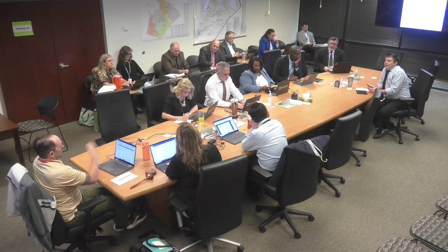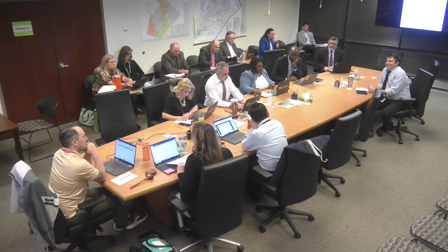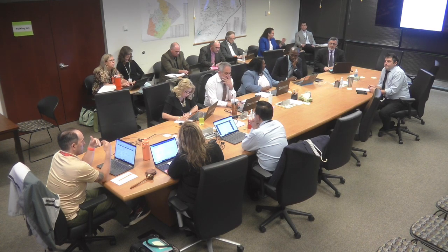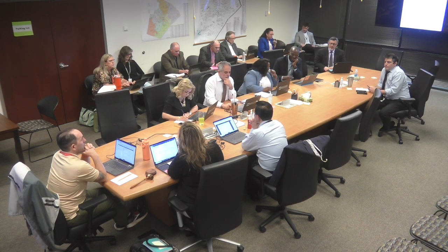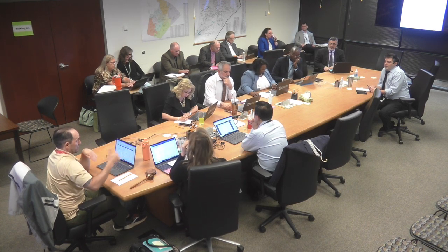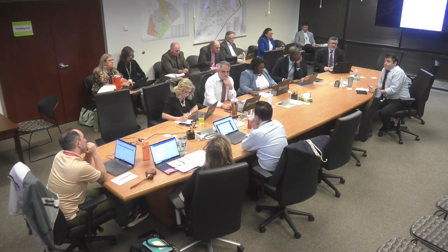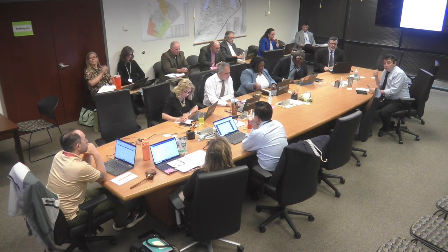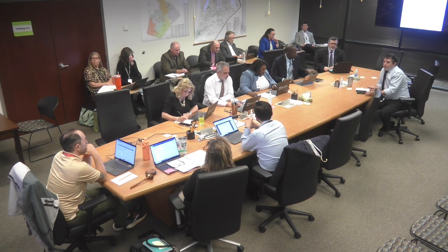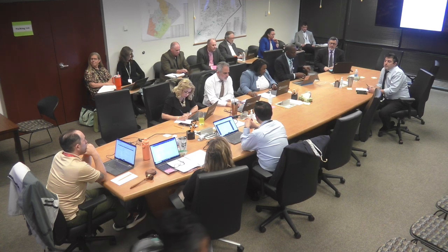So I'm going to use Broughton because Broughton had the HVAC problems. Staff at the school, the principal or whomever, they get to a Friday, they can't have the AC run on Saturday just to check it? I'm sure they could request that, but when it comes to outdoor temperatures, if it's around 55 degrees, the system won't necessarily kick into a cooling mode, even if we tell it to be on. We would have to manually force things to run. Okay.